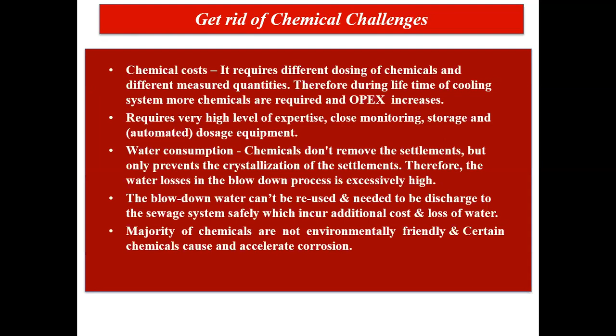But what the chemical actually does is it doesn't kill the problem, it just doesn't allow the calcium to settle. It keeps it in suspended form so that it doesn't settle. So you are actually increasing the TDS, total dissolved solids, also. The chemical itself has some TDS value, plus it's not allowing calcium to settle, so TDS increases further. This means you need to excessively blow down the water. And obviously, these chemicals are not environmentally friendly, and can sometimes accelerate corrosion.